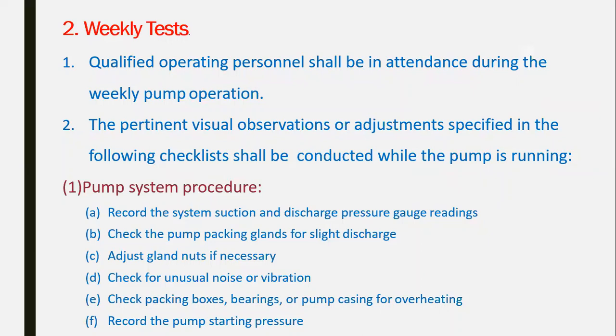Number one, a qualified operating person has to attend during the weekly operation and testing of the pump, starting with the visual observation and adjustment as specified below. What you have to do: recording the system suction and the discharge pressure gauge reading, suction from the water tank and the discharge from the common headers. What is the pressure rating? Check the packing gland. Adjust the gland nuts if necessary. Checking unusual noise or vibration.